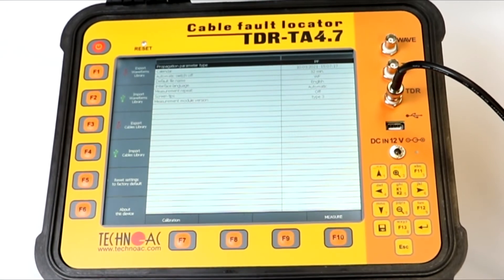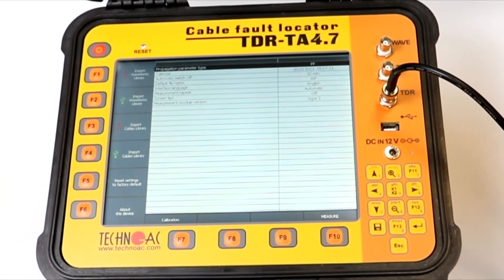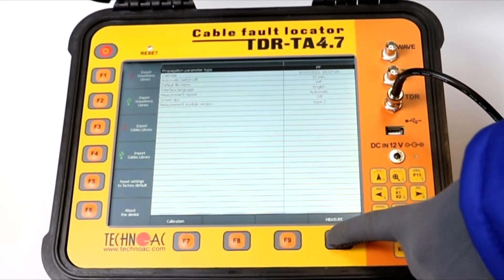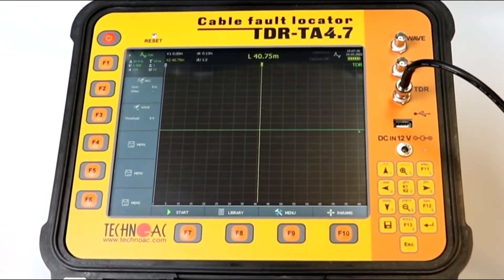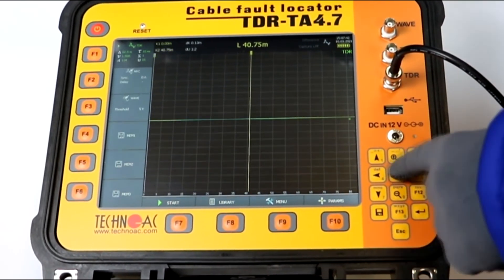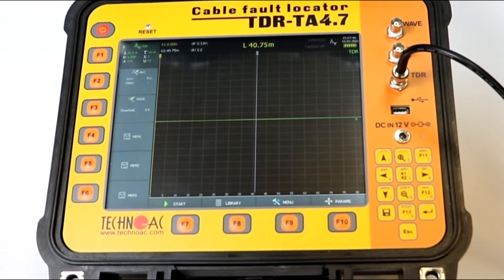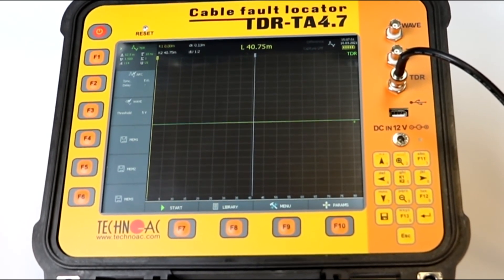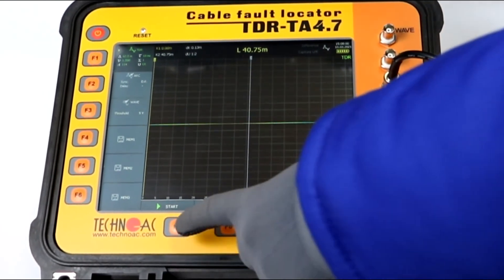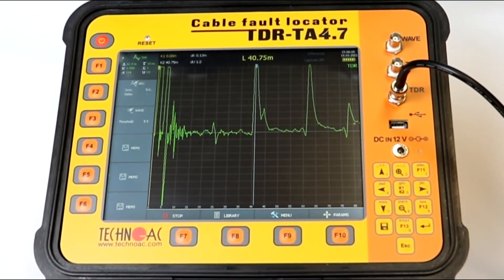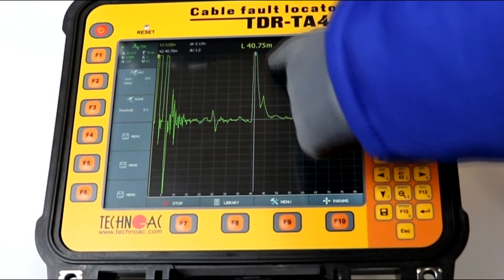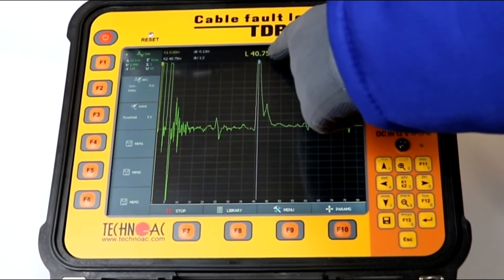When the device is on, we can see its main menu. In order to start the fault location, we will press the F10 button, which starts the measurement. When we press the Start button, we can see the main measurement screen, and we can see two cursors — Cursor 2 and Cursor 1. These are the two points between which the TDR will measure the distance. We press Start to begin location, and as you can see, we have a diagram here. We can also see the distance to the most significant difference in the graph — 40 meters.